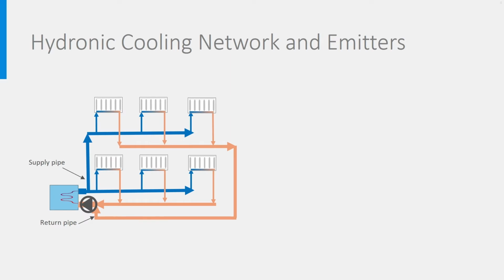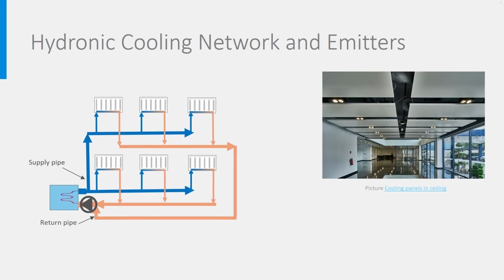The hydronic network will be identical to the network in heating mode, where here too a parallel design is recommended in such a way that the same temperature levels are guaranteed in all emitters. What do these emitters look like? Mostly, cooling panels in the ceiling are applied, like in this figure, where chilled water circulates in small ducts at the upper side of the panels. Sometimes floor cooling is applied too, which looks exactly like floor heating.